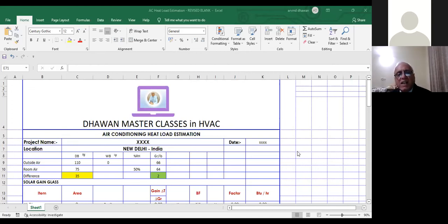So the standard design takes the bypass factor as 0.1. We assume 90% of the air will come into contact for heat transfer, and about 10% will not come into contact for heat transfer. So for normal comfort applications, we take it as 10%. Now, suppose you have a special application, with a very low dew point and all the factors involved, then the coil is specially designed by the manufacturers to make the bypass factor less than 0.1. Normally, for normal comfort air conditioning, the fins per inch, the size of the tube, and all these things are designed for a standard application as 0.1.